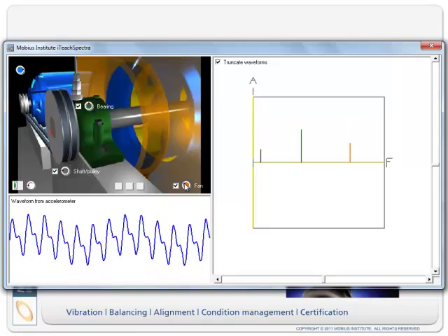Now, normally the spectrum isn't color coded this way. You will just see it all in one color. And you have to go through some effort to actually identify what these peaks mean. But the easiest thing to do first is always identify this one X peak and say, well, this is my shaft turning speed. In this case, it's not the motor shaft speed, but it's this fan shaft speed. So we can say this is one X. This is my once times revolution of this shaft.